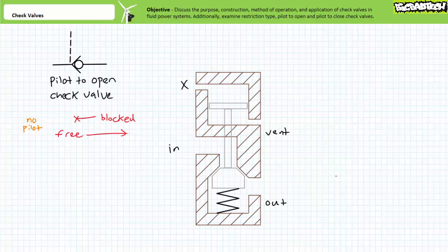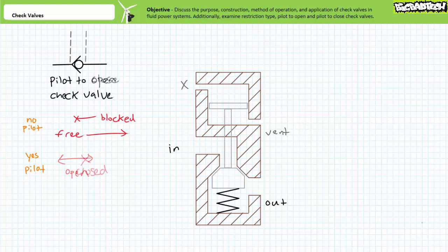One direction is blocked flow, one direction is free flow. In the presence of a pilot signal, the check valve opens and both directions allow free flow. Pilot to close check valve is just the opposite. As the name implies, it acts like a regular check valve in the absence of a pilot signal — one direction is free flow, the other direction is blocked. In the presence of a pilot signal, the check valve closes and both directions are blocked.